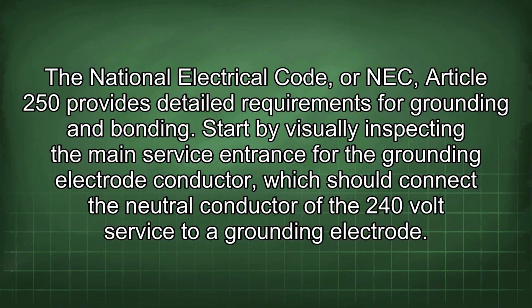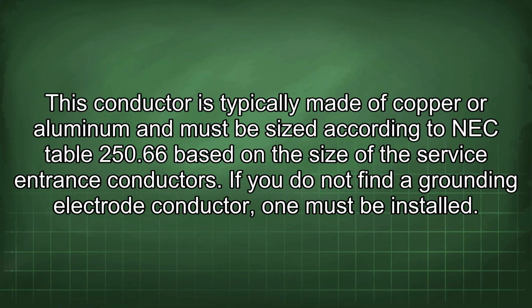Start by visually inspecting the main service entrance for the grounding electrode conductor, which should connect the neutral conductor of the 240 volt service to a grounding electrode. This conductor is typically made of copper or aluminum and must be sized according to NEC Table 250.66 based on the size of the service entrance conductors. If you do not find a grounding electrode conductor, one must be installed.